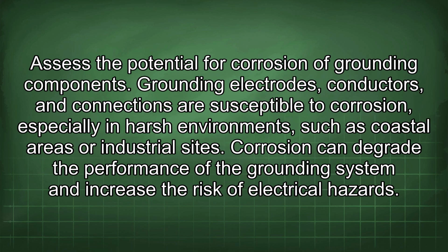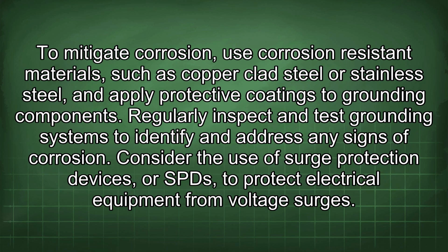Assess the potential for corrosion of grounding components. Grounding electrodes, conductors, and connections are susceptible to corrosion, especially in harsh environments such as coastal areas or industrial sites. Corrosion can degrade the performance of the grounding system and increase the risk of electrical hazards. To mitigate corrosion, use corrosion-resistant materials such as copper-clad steel or stainless steel, and apply protective coatings to grounding components. Regularly inspect and test grounding systems to identify and address any signs of corrosion.